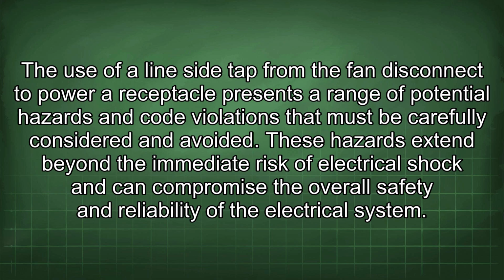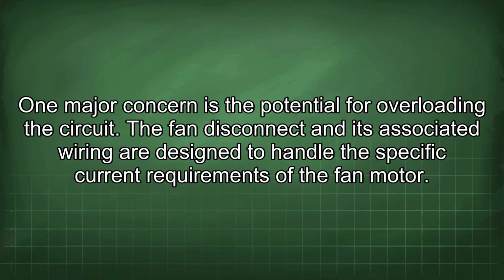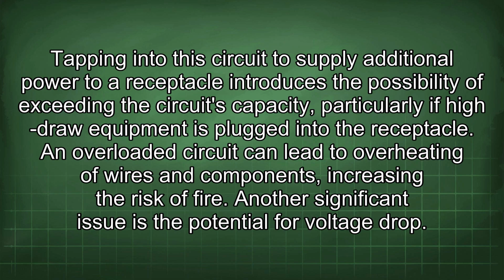The use of a line-side tap from the fan disconnect to power a receptacle presents a range of potential hazards and code violations that must be carefully considered and avoided. These hazards extend beyond the immediate risk of electrical shock and can compromise the overall safety and reliability of the electrical system. One major concern is the potential for overloading the circuit. The fan disconnect and its associated wiring are designed to handle the specific current requirements of the fan motor. Tapping into the circuit to supply additional power to a receptacle introduces the possibility of exceeding the circuit's capacity, particularly if high draw equipment is plugged into the receptacle.